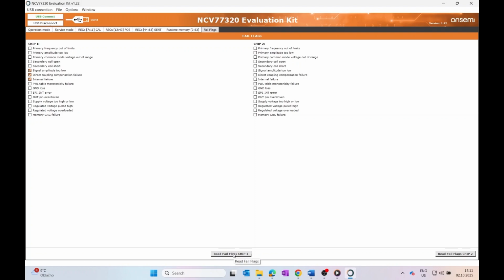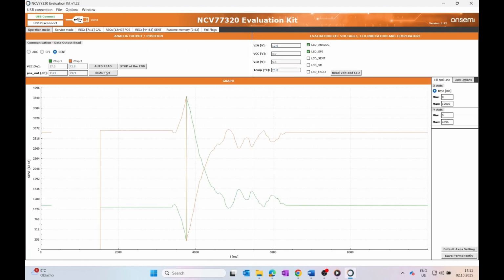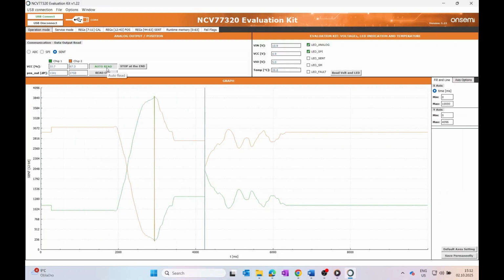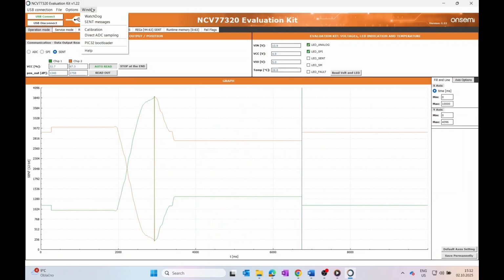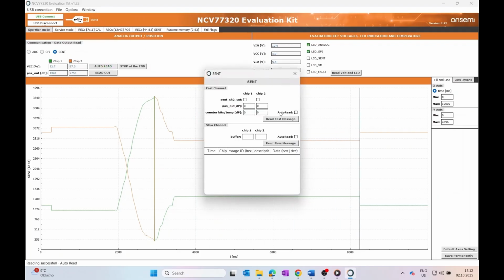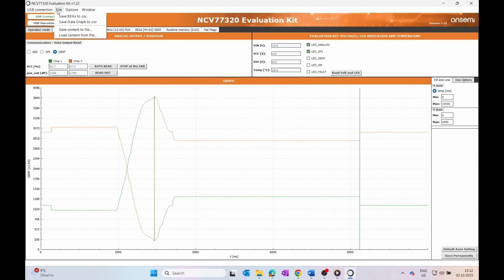After reattaching the rotor, the registers should be read twice, as the failure flag register is latched and only clears upon readout, allowing normal operation to resume. If the SENT interface is used, the SENT Messages window can be opened to read fast and slow channel data from both devices. The slow channel must be enabled in the EEPROM to function properly. To save the current position plot, click Save Data Graph to CSV. To store the current sensor configuration, click Save Content to File. The saved configuration file can later be loaded into the GUI and reprogrammed to the device if needed.